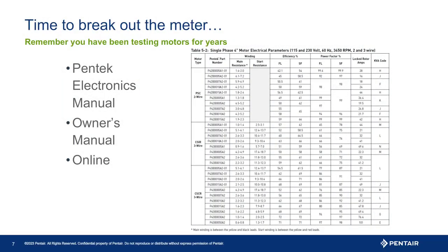If it is not the wire, well, time to break out the meter. And I know in the beginning we said no meters. Well, let's first look at what we have done. We did no meter testing, simply proofing the programming, checking the wire connections, and isolating the issue. Now the issue is isolated, it is time to do what we have done in our industry for years. Pull out the winding and ground test data for the motor and do the ohm testing you should be familiar with. Notice we are not testing the drive, because the drive did not show a high amp fault without a motor. So yes, you may need to eventually use a meter, but it is not the first step.